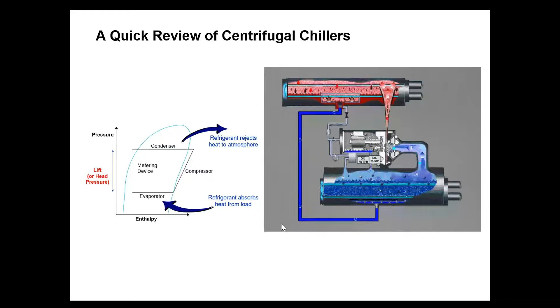Now we know that there are two processes happening inside the centrifugal chiller, and they are influenced by two external factors. Of course, one factor is the conditioned space. If there is evaporation happening, that means the refrigerant is picking up heat somewhere and rejecting that heat to the cooling tower. So in the bottom representation, the evaporation is basically the chilled water coming from the air conditioned space at maybe 12 degree C. That heat is picked up in the evaporation process by the refrigerant, then it gets compressed and goes to the condenser line, and that heat picked up through evaporation is rejected in the cooling tower.